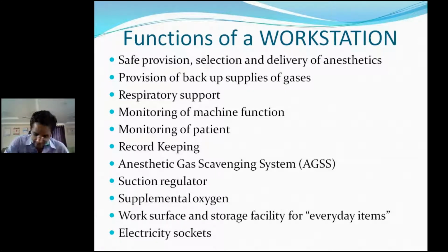So what is record keeping here? It is nothing but maintaining the patient's blood pressure, heart rate, mean arterial pressure, oxygen saturation, and even the abnormalities in the ECG waveforms, such as PVCs or VPCs, that means premature ventricular contractions. It also records the missed beats in the latest advanced machines. And there is an anesthetic gas scavenging system.